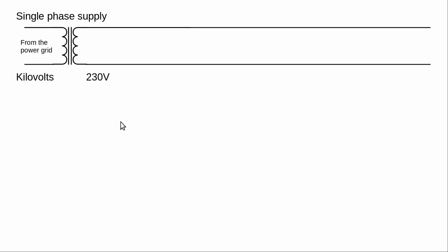building. So at this point we have those two wires and they are completely interchangeable. There's nothing special about the top or the bottom wire, and there's no way to distinguish them. As long as you have both wires, you can get 230 volts power. Since it's AC, of course it has to be AC, otherwise it wouldn't go through the transformer. There is no plus or minus. It's just two wires carrying AC current. So why do we need to name them differently?